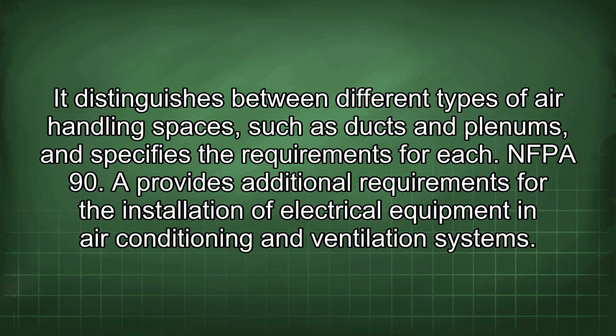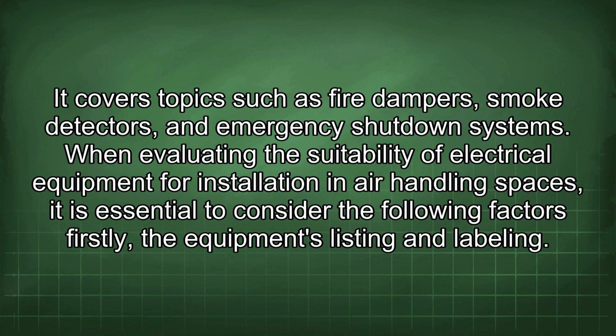NFPA 90A provides additional requirements for the installation of electrical equipment in air conditioning and ventilation systems. It covers topics such as fire dampers, smoke detectors, and emergency shutdown systems. When evaluating the suitability of electrical equipment for installation in air handling spaces, it is essential to consider the following factors. Firstly, the equipment's listing and labeling.